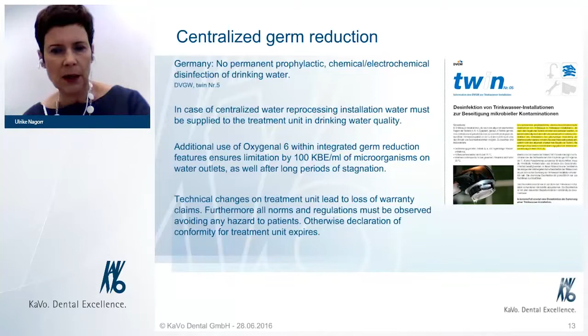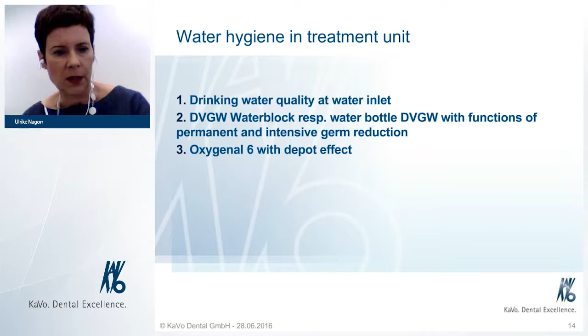So water hygiene in the treatment unit, that means patient water, is based on having supplied drinking water quality at the water inlet. That means you first check the hardness or the softness of your water in your region. You discuss with your engineer, with your distributor, how some regional problems could be solved, and then you select either the big water block DVGW or the water bottle with the functions of permanent and intensive germ reduction to provide drinking water quality for the patient's water in spray cooling, the syringe or the cup filler. And the chemical which is being used is the Oxygenal 6 with depot effect because of the silver ions therein.